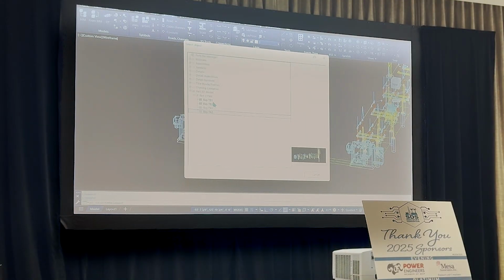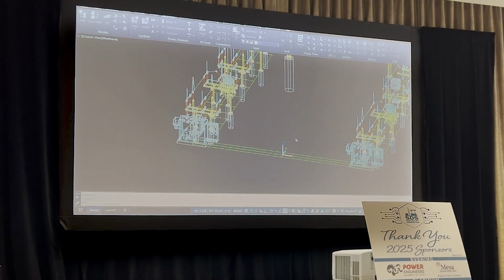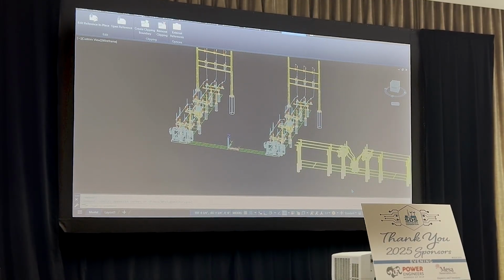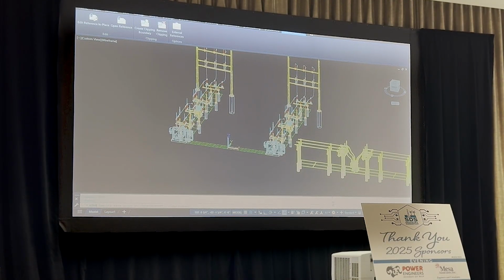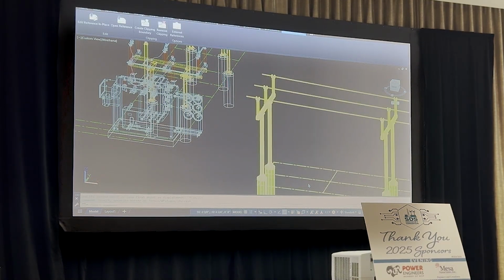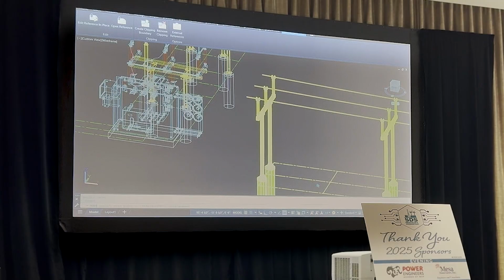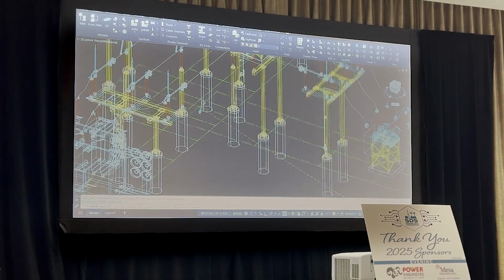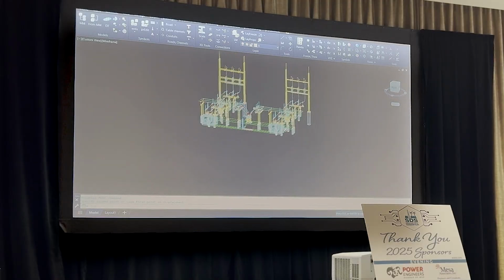I'm going to go ahead and place transformer 2 over here. And then I'll go ahead and place my tie bays, and I'm going to drop these so I can grab a different point. But I'll drop that one here, and then move it with, not that point actually, but this one, because it sits in the center of this bus support over here, and those two mate together, right? So now we have that bay, and then we can place this other one.